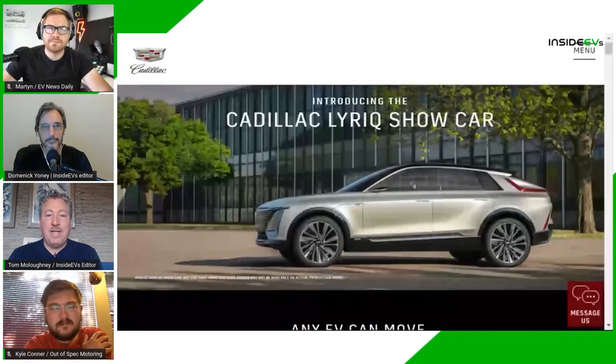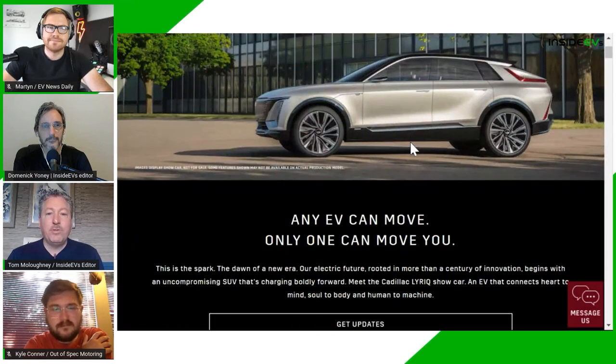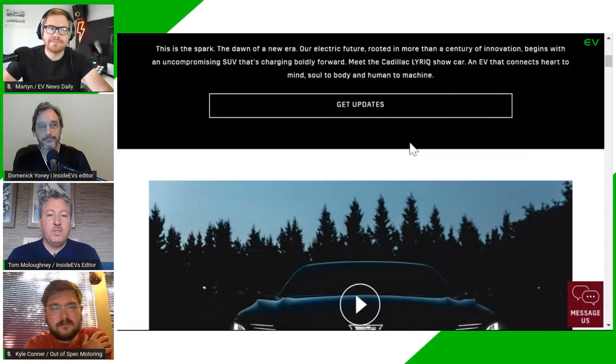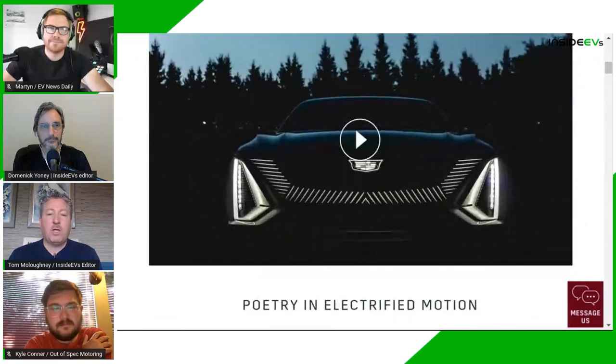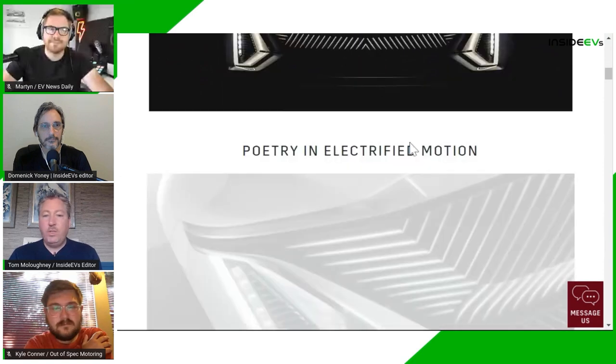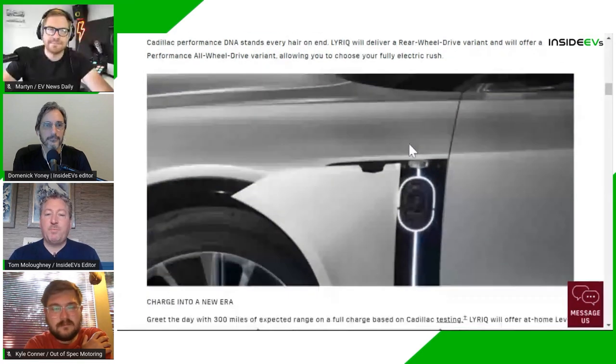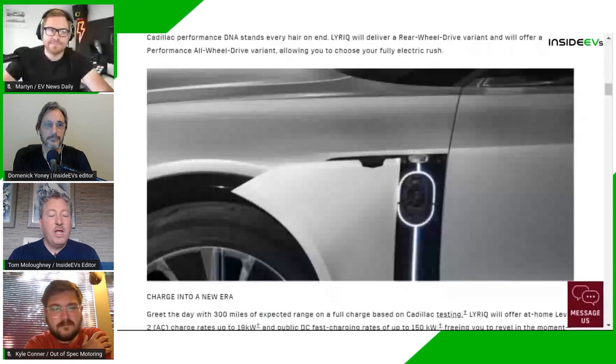And even, you talked about the 19 kilowatt onboard charging. The electric is different in the U.S. as it is in Europe. You've got your three-phase power. But here in the U.S., Tesla tried this already, with the dual onboard chargers, and they realized it was not worth doing, because here in the U.S., you need a 100-amp dedicated circuit to have 19.2-kilowatt AC charging. Almost nobody has that here. So Tesla abandoned it because it created too many problems with their customers. People were ordering it, and then they realized they couldn't install the charging in their house. Then they were mad at Tesla for selling it to them on something that they needed to spend $6,000 to upgrade their house electricity in order to use it.